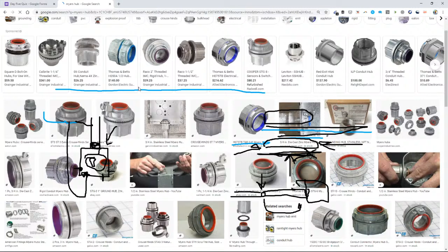There's a special component called a Myers Hub that fits right into the top of the box, and it has more metal, a more robust clamp. Myers Hubs are what's necessary when going into the top of a box. In fact, an inspector told me that a Myers Hub is needed not just for the top of the box, but anywhere on the top or side where water can get into the box and drip down inside. Otherwise, you'd use a rain tight fitting anywhere else on the box. So entering the top of an outdoor rated box, you need to use a Myers Hub.